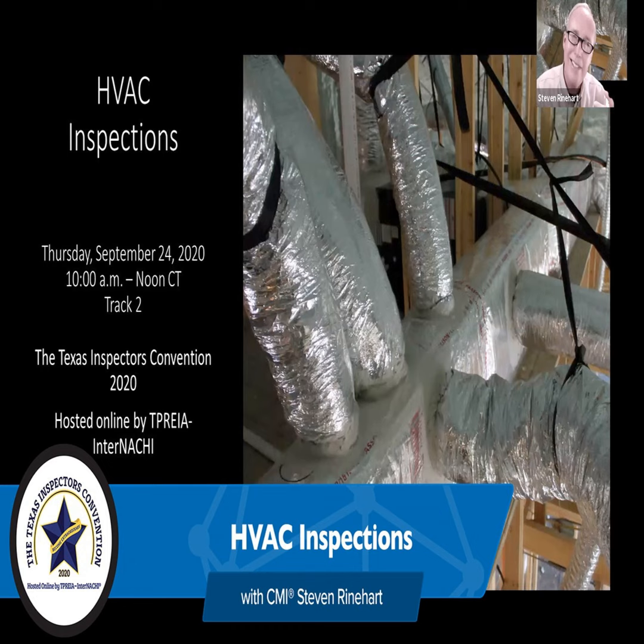Lack of protection. In the garage, I know here in Texas, in our area, if you see it in the garage, it's not sitting on the floor. It'd have to be raised 18 inches anyway. We usually see it in the closet. I don't care for them out in the garage, open access to the garage, because the air handler typically leaks, ends up sucking garage fumes into the air. It's just a bad place to put the unit.